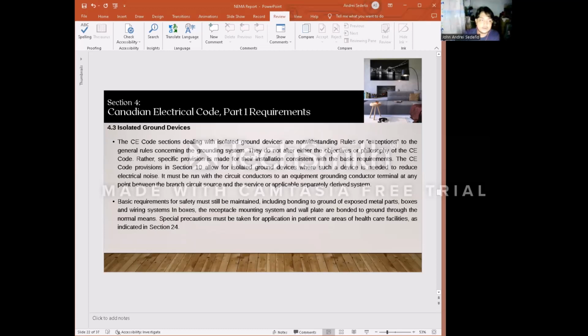Now, for isolated ground devices, the code sections dealing with isolated ground devices are, notwithstanding, rules or exceptions to the general rules concerning the ground system. They should not alter either the objective or philosophy of the CE code. Rather, specific provision is made for their installation consistent with the basic requirements. The CE code provisions in Section 10 allow for isolated ground devices where such a device is needed to reduce electrical noise.